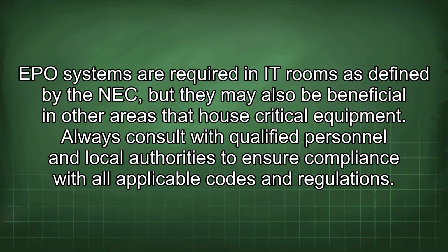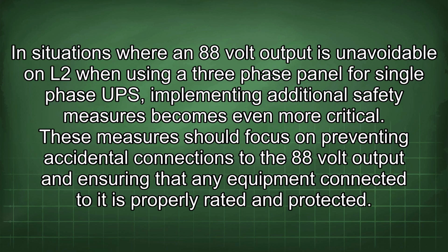Always consult with qualified personnel and local authorities to ensure compliance with all applicable codes and regulations. In situations where an 88-volt output is unavoidable on L2 when using a three-phase panel for single-phase UPS, implementing additional safety measures becomes even more critical. These measures should focus on preventing accidental connections to the 88-volt output and ensuring that any equipment connected to it is properly rated and protected.